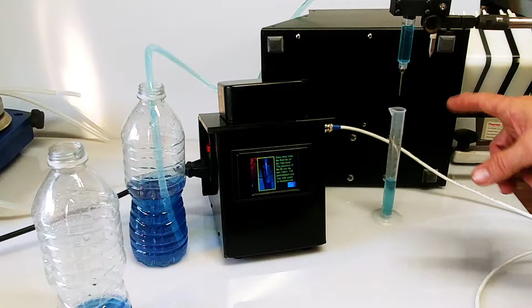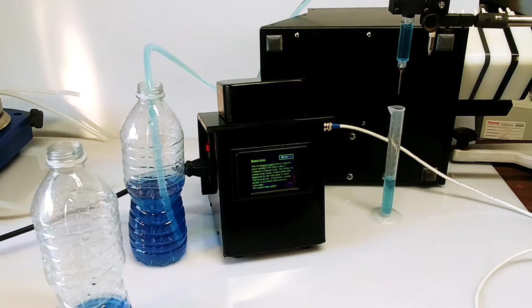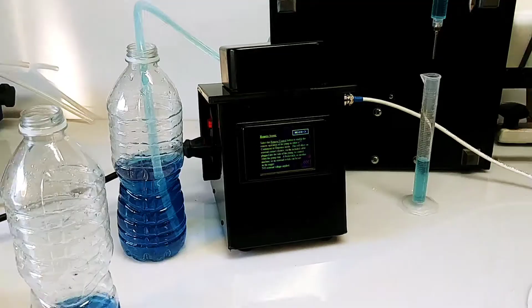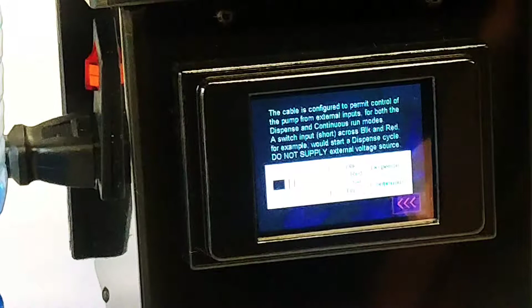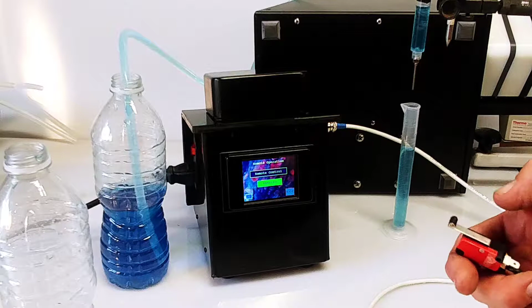And then lastly, in a remote mode, you can go in, and if you look at the help screen here, in remote mode, you'll see that it gives you actually a wiring diagram for how this cable that comes from the manufacturer and is supplied with the unit is set up. So we could use that information to go ahead and wire a switch into the unit, which we did for the purposes of this demo. We hooked up just a regular switch, and now when you hit the switch, the system runs and it dispenses the preset value. It's kind of a cool little feature.